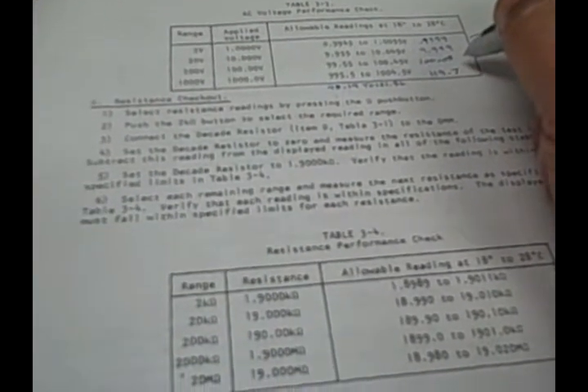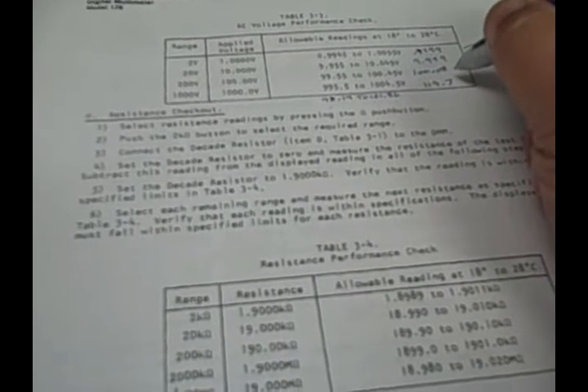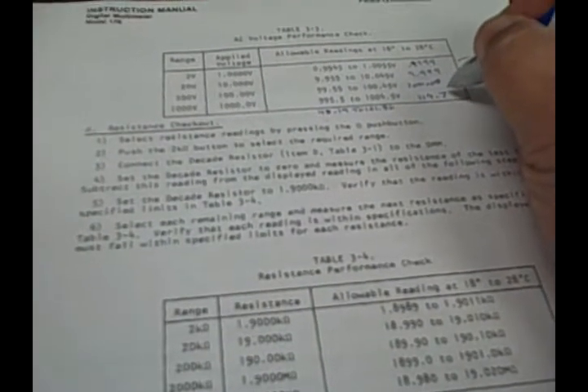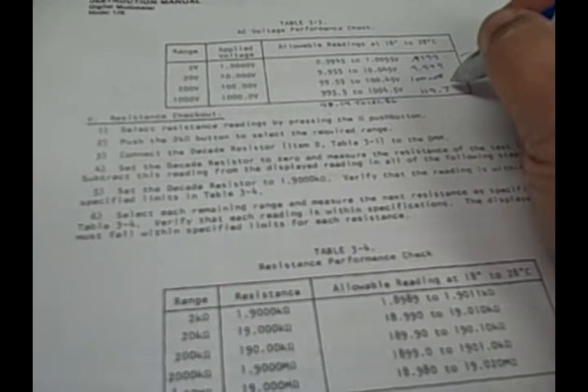So well into the middle, and within 0.3 of a volt of being perfect at the 1,000 volt range. So we are within the allowable readings, and we passed the performance test using the 120 volts on the 1,000 volt range. Wish I could go to the 1,000 volts AC. I just don't have the equipment to do it, and that's the best we can do. We're going to move on to resistance now.